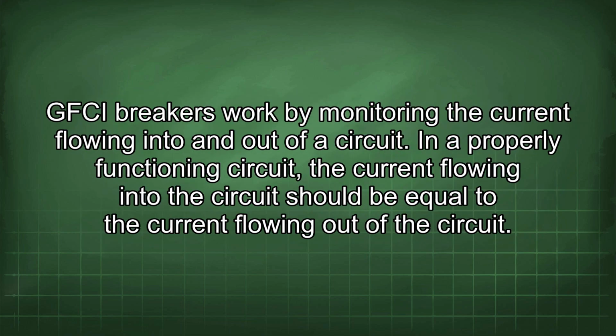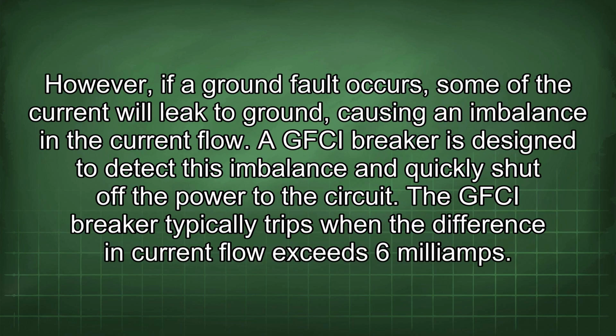GFCI breakers work by monitoring the current flowing into and out of a circuit. In a properly functioning circuit, the current flowing into the circuit should be equal to the current flowing out of the circuit. However, if a ground fault occurs, some of the current will leak to ground, causing an imbalance in the current flow.